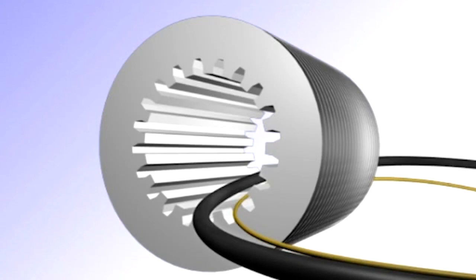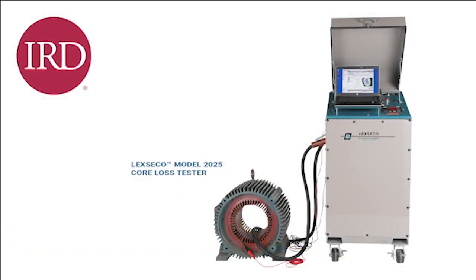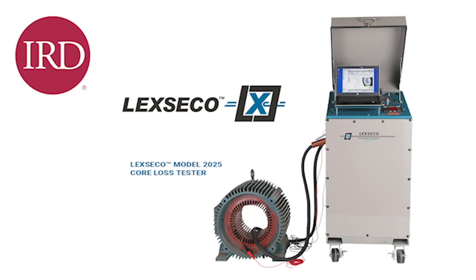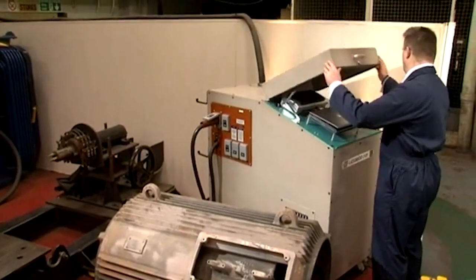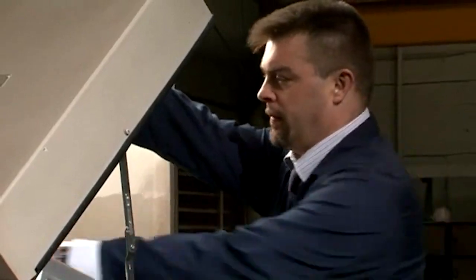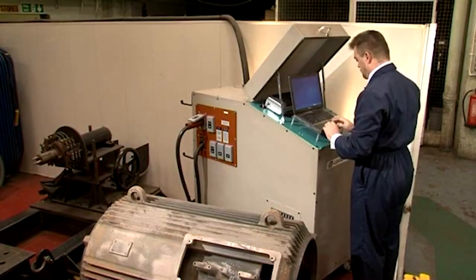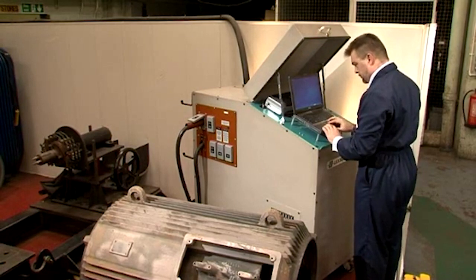The process can also be used to identify the position of any hot spots. The IRD Lexseco family of core loss testing products available in a range of capacities is the leading solution providing end users and motor repair organizations with a quick and efficient process to determine the condition of cores during inspection and repair procedures.